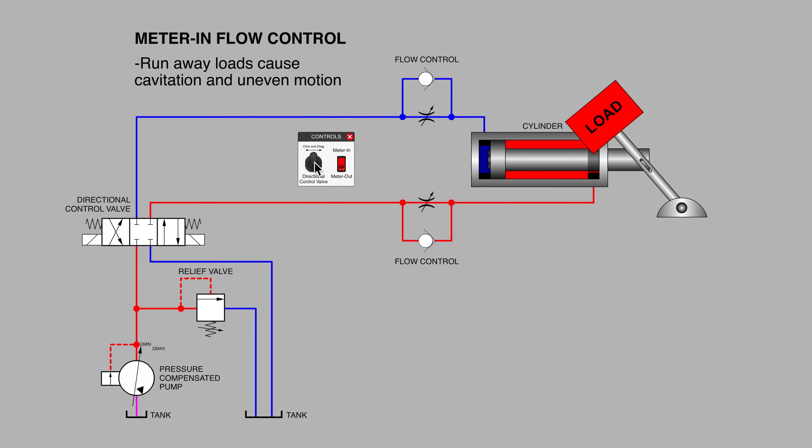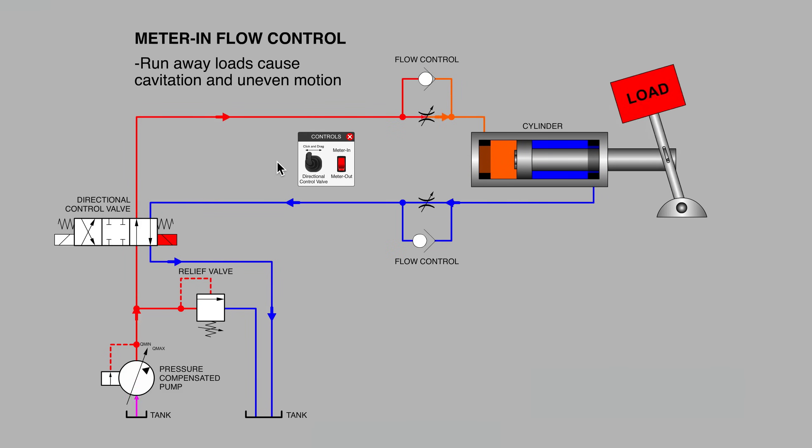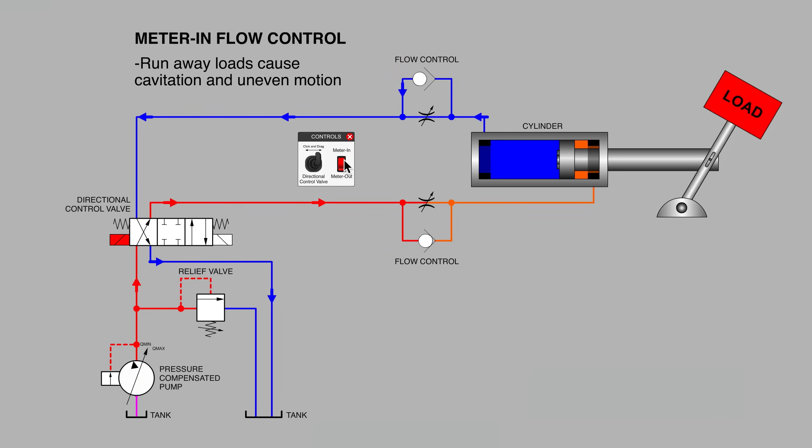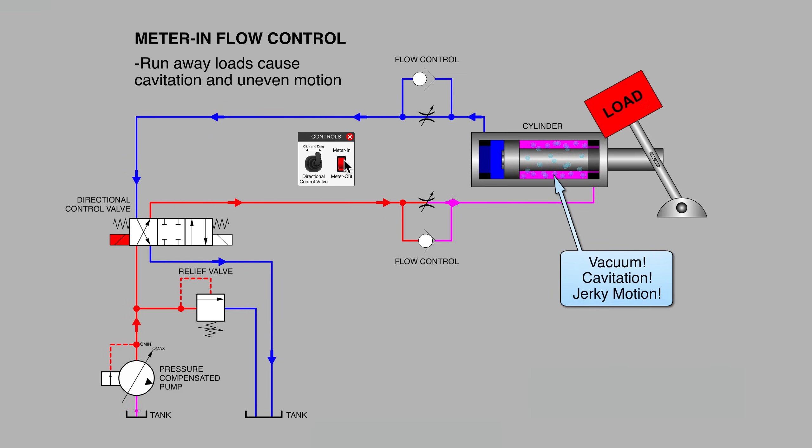So as you can see, meter in will work fairly well as long as there's no runaway effect. In fact, meter in will work best in the vertical position for extending the cylinder if you had gravity and a load opposing the extension of the cylinder.